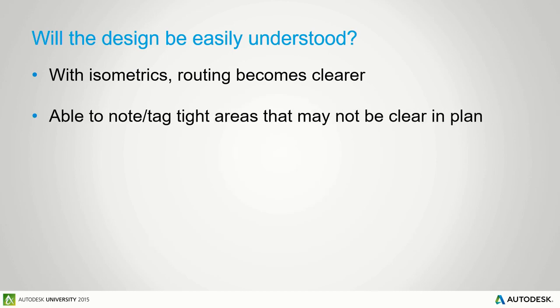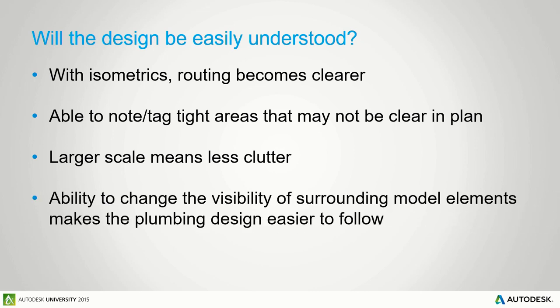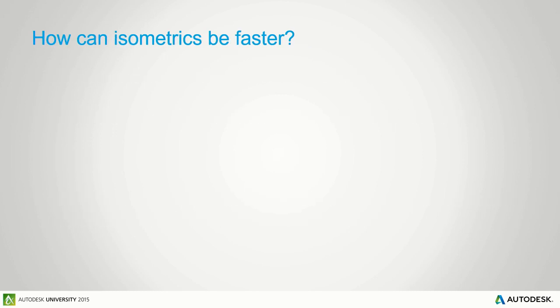You're able to tag and note tight areas that may not be clear in plan because you have everything else in the way. Where plans don't have space for all those notes and dimensions, using an ISO you're able to create space for yourself to put those tags in. You're also able to display and tag stacked pipe because it's a 3D view. Having a different, larger scale means less clutter and more space for tagging and noting. Within Revit you also have the ability to change visibility of the surrounding model, making the plumbing design much clearer.